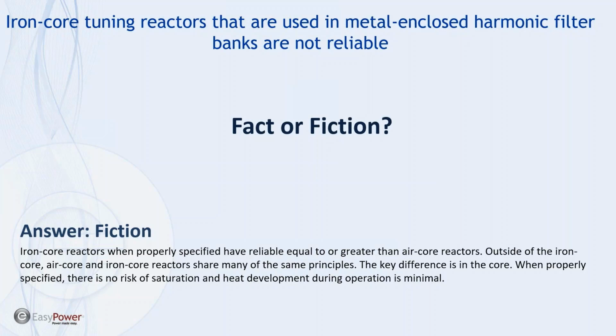At the harmonic, if for example at the 5th harmonic with a 5th tuned filter reactor, maybe your harmonic analysis determined that your harmonic current would be, say, 30 amps. So remember, fundamental 100, we calculate 30 amps at the 5th harmonic. We would not design that reactor for 30 amps. We would most likely design that reactor for 60 amps. In some cases, depending upon the type of system, we might even go up to 100 amps. So we could set the reactor harmonic current rating equal to the fundamental frequency current that's expected through that reactor. So again, we're adding significant margin into the design.